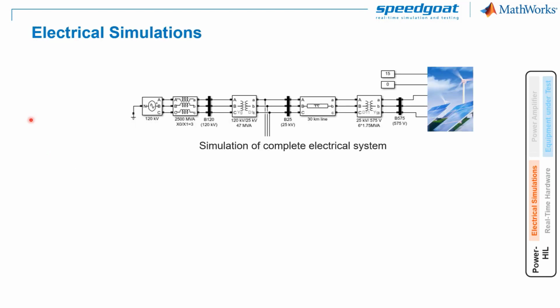Sure, Carlos. On this slide, we can see a model of a solar panel or a wind turbine that uses an inverter for the connection to the grid. Now, if we want to test a real inverter, which is, for example, under development, it would be very risky to do that against the real grid, since it might not have been tested thoroughly yet.